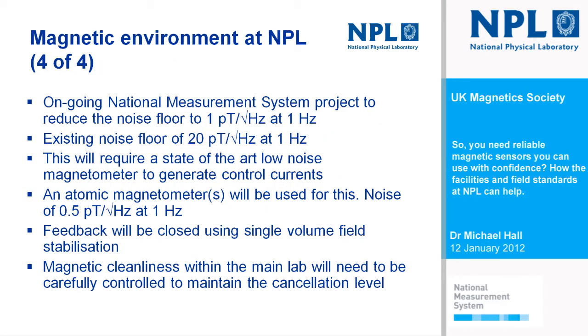So what we're doing at the moment is lowering that noise floor with a target of 1 picotesla per root hertz at 1 hertz, and comparing that to the existing noise floor. That red line in the graph I showed earlier is 20 picotesla per root hertz. To get it down to 1 picotesla per root hertz, we need a considerable improvement, and the flux gate magnetometer that's used has an inherent noise floor that is measured and known to be 7 picotesla per root hertz. So we have to move to a magnetometer technology that has a noise floor of 1 picotesla per root hertz or better.